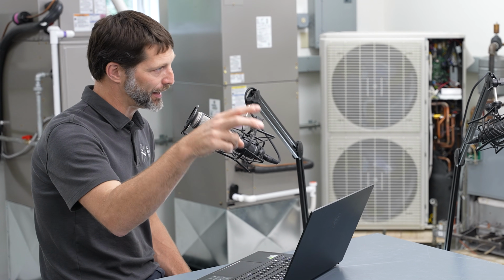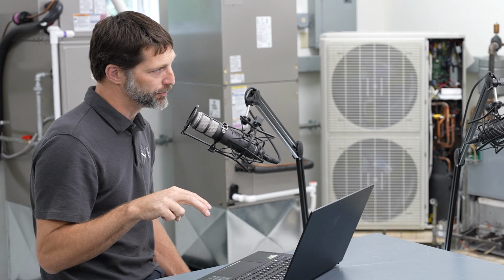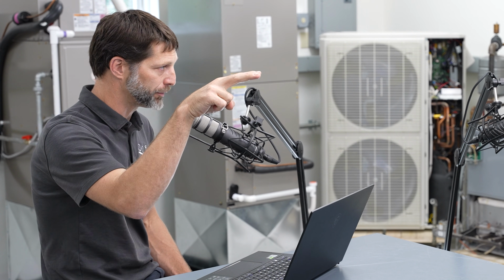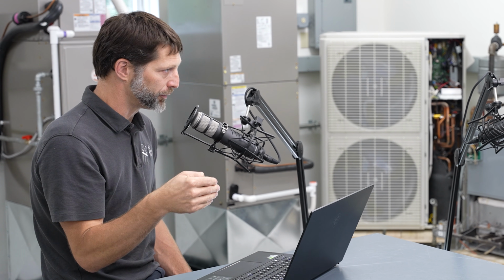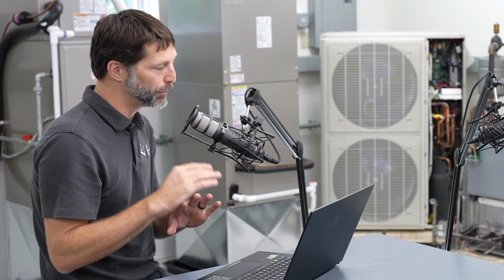So if that's the case, or maybe there are no service valves at the indoor unit, it's just flare adapters or braze joints, whatever. After looking at that, making sure everything's open and sealed, you go to the outdoor unit, then you have to look at, does the outdoor unit have master service valves as well as service valves for each zone? Some systems have a pair of master service valves, and then it's just flare adapters for each zone. So each one's different. Now, most dual zone systems don't have master valves, and they just have a pair of service valves for each zone.